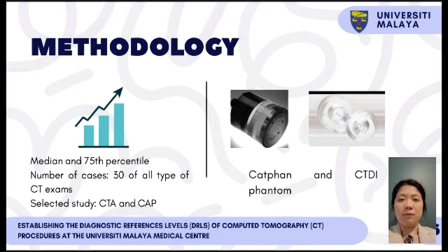To validate our findings, we will meet our two secret agents, the Catphan phantom, which helps to evaluate image quality across various CT machines, and the CTDI, a radiation detective. Together, they help us uncover how protocols behave on the same machine and across different machines. First, we study how specific protocols affected both image quality and radiation dose on the same machine. This allows us to fine-tune the balance for optimal performance.